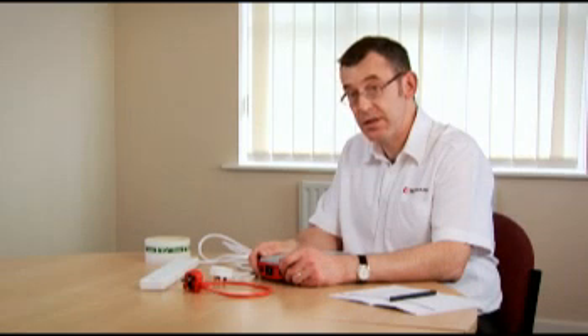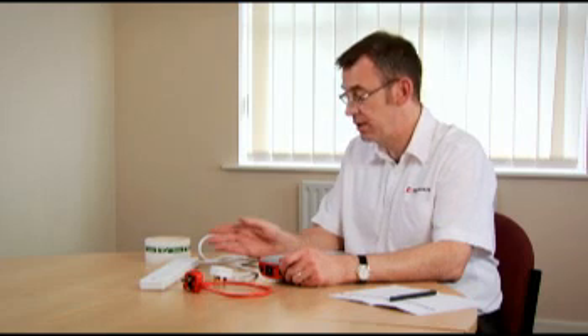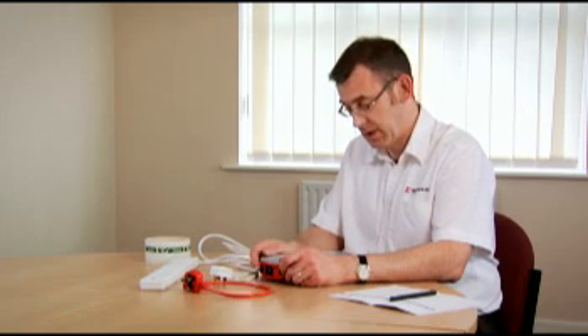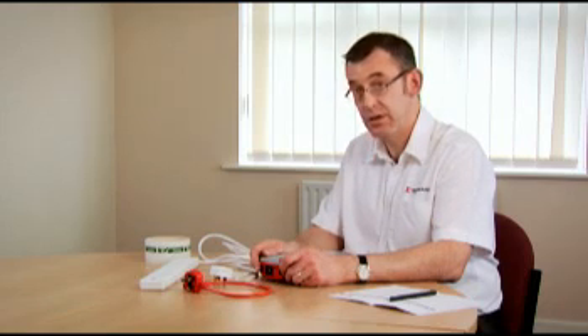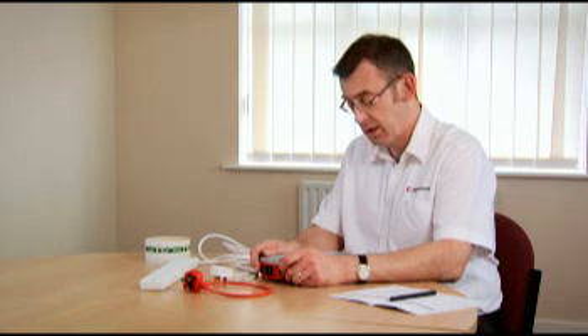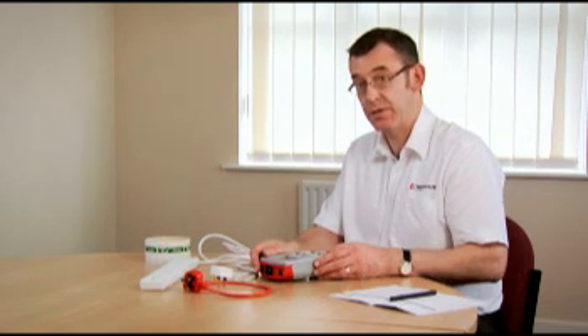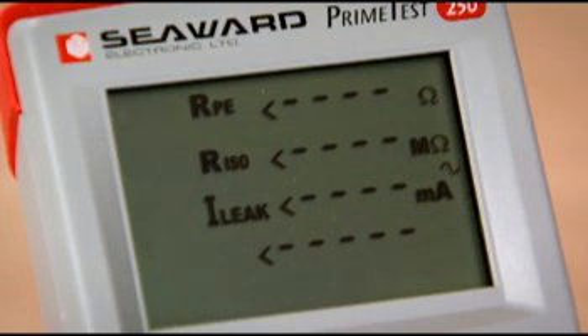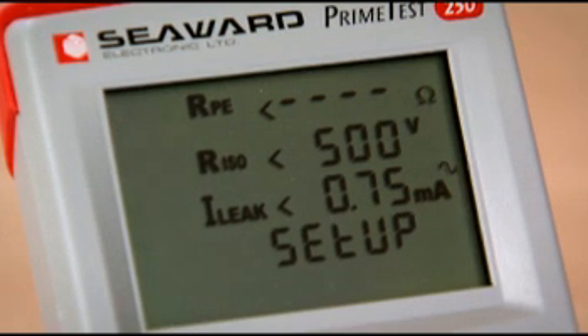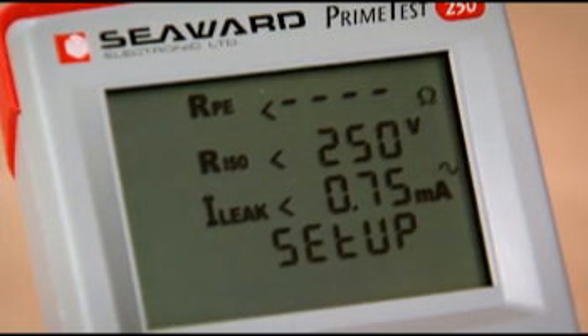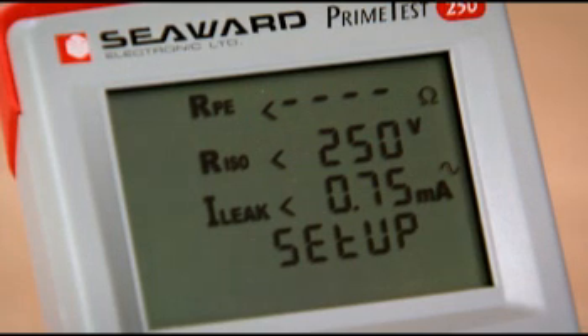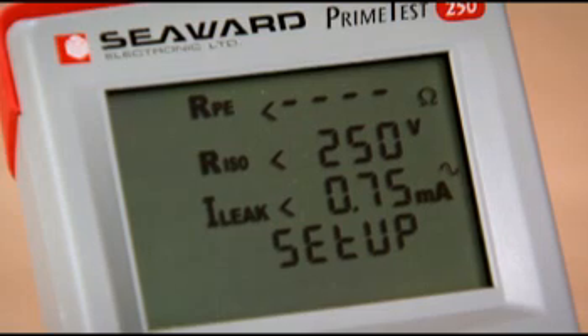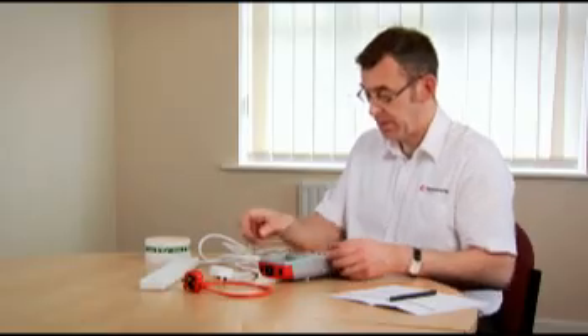We're now going to use the tester to test this surge-protected multi-way adapter. Now, because it's surge-protected, we're going to change the insulation test voltage from 500 volts to 250 volts. That's easily done by pressing the setup key, pushing the Class 2 key, changing the voltage from 500 volts to 250 volts. Press the setup key to go back to the test mode.